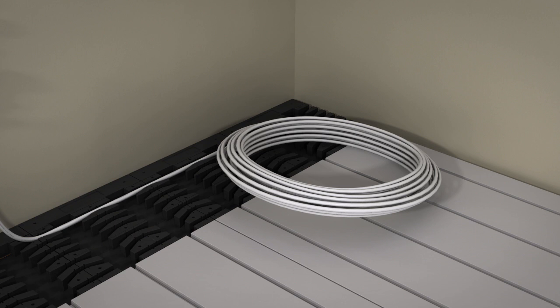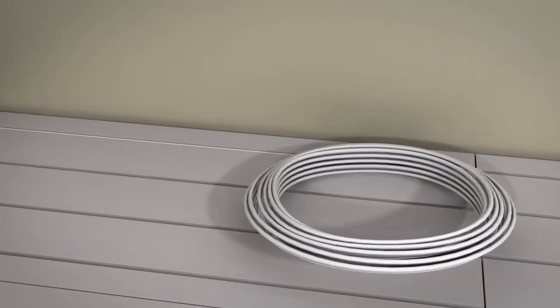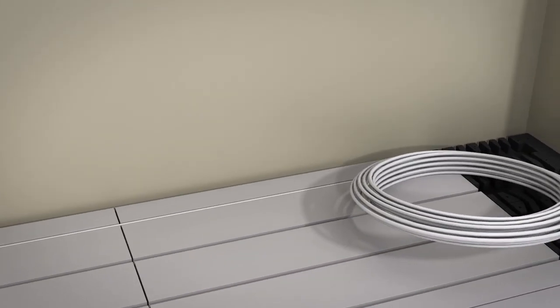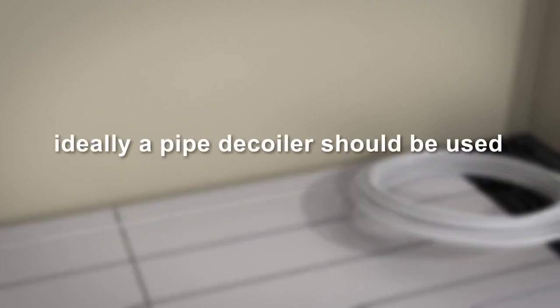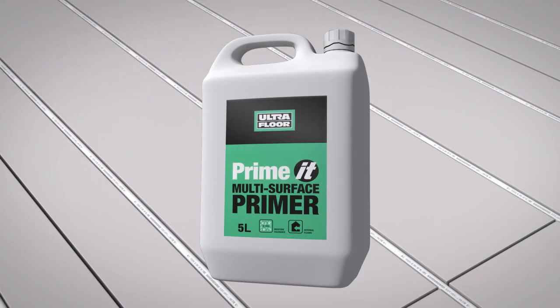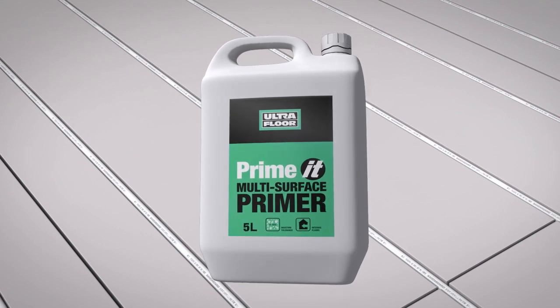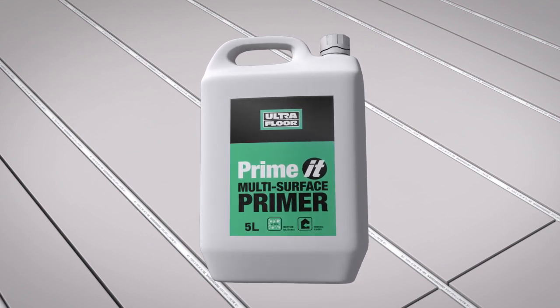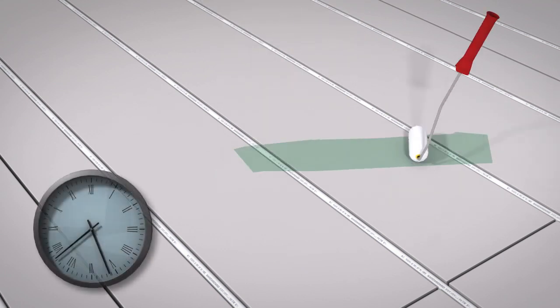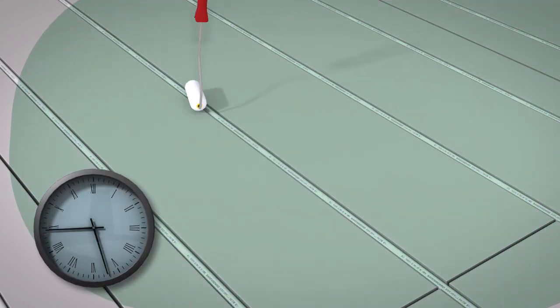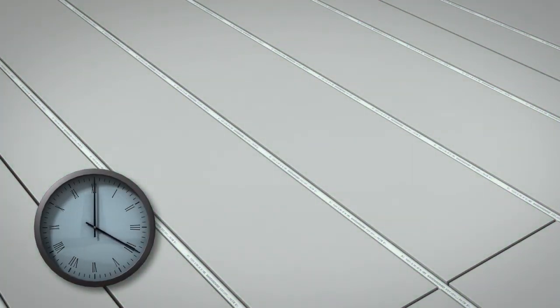For ease of installation, lay the pipe flat and unroll whilst the coil is on its side, not with the coil in an upright position. This ensures that the pipe does not spring out of the board's grooves. Ideally, a pipe decoiler should be used. The panels can then be primed using the Ultra MSP Multi Surface Primer. The primer can take between 30 minutes and 3 hours to dry, depending upon room temperature.